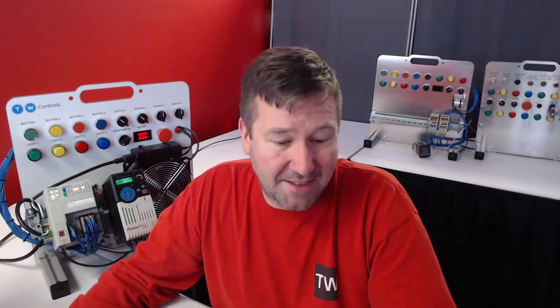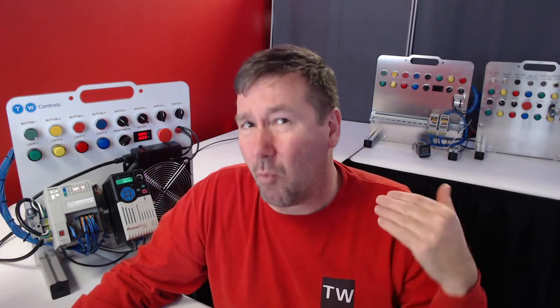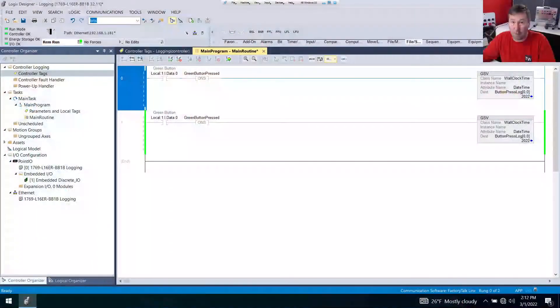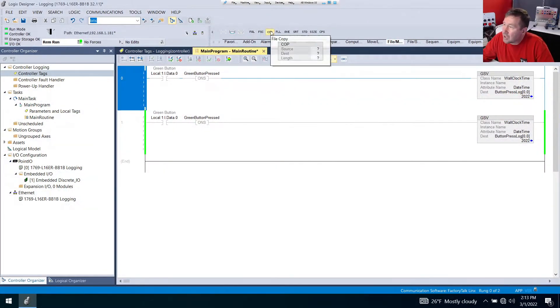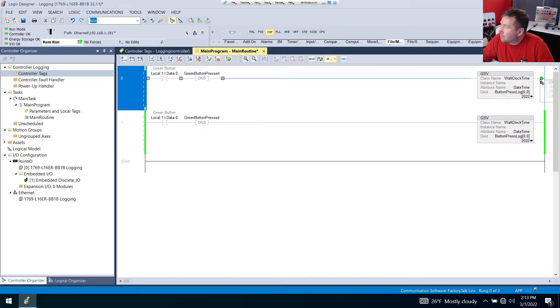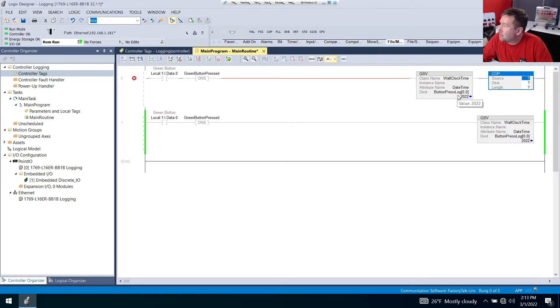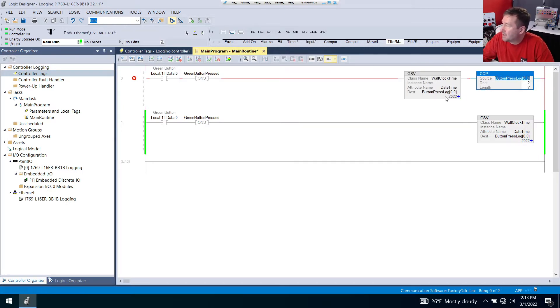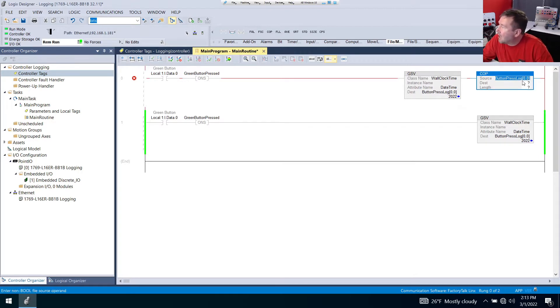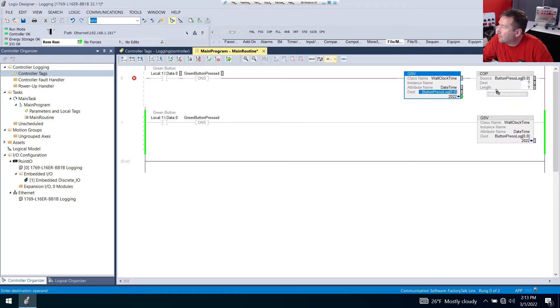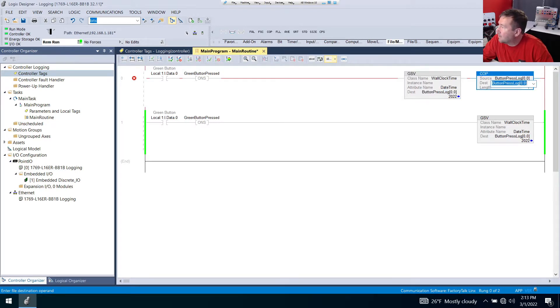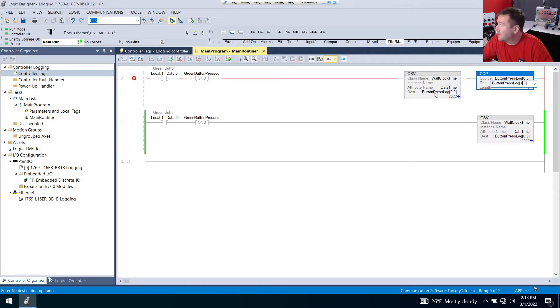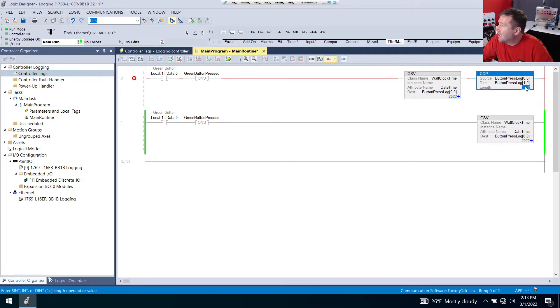So all we've got to do is add some code to this to shift it around. First, let me show you how not to do it because a lot of you do this and then you contact me and don't understand why it doesn't work. So this is an important exercise. We're going to bring down a copy instruction. And what you think you want to do is you want to copy our source, which is button press 0,0, and you want to copy to a destination of the next element, which in this case is going to be button press log 1,0.